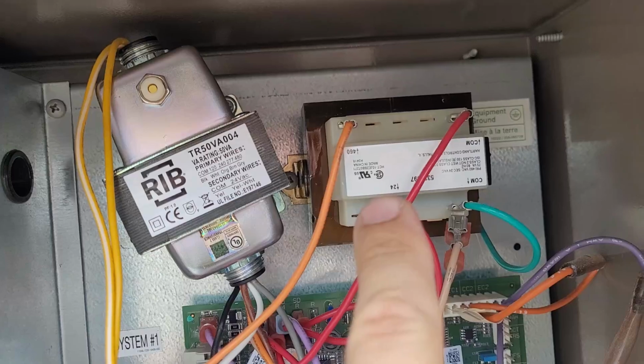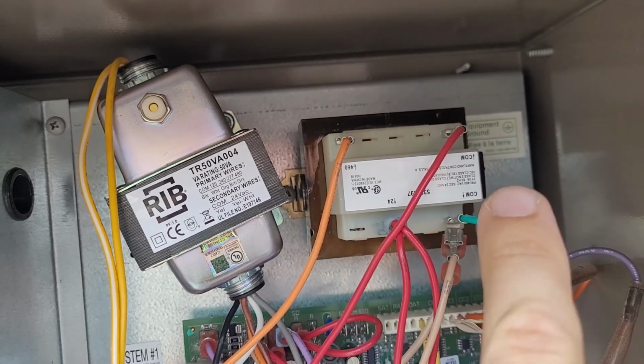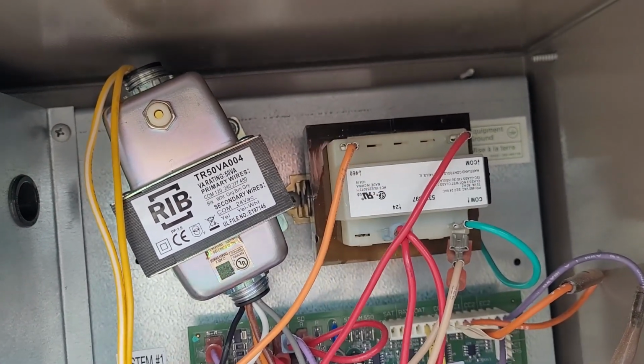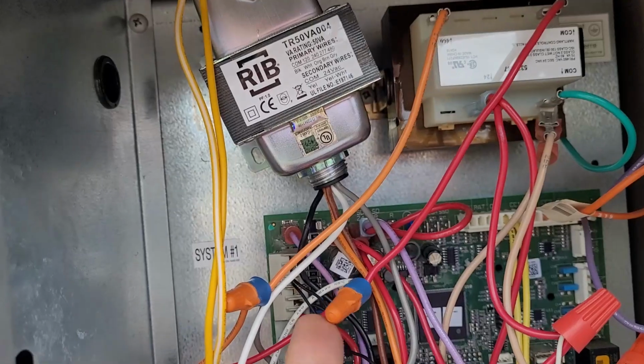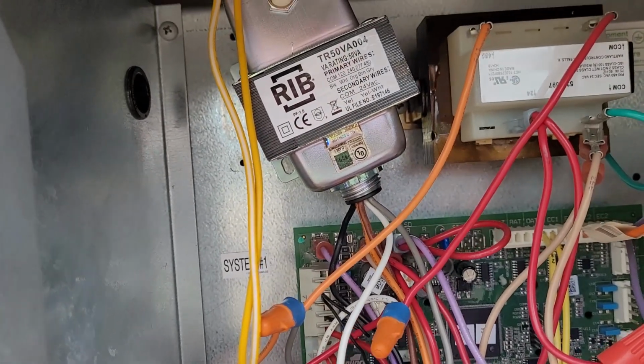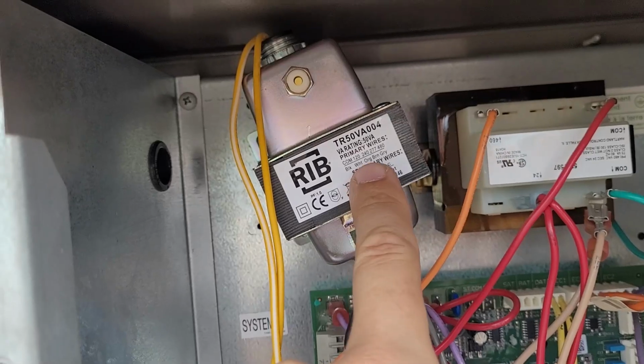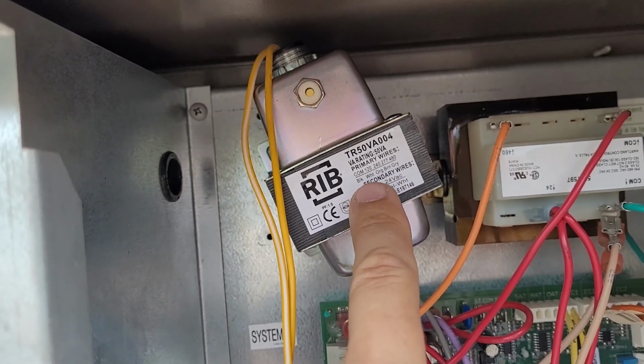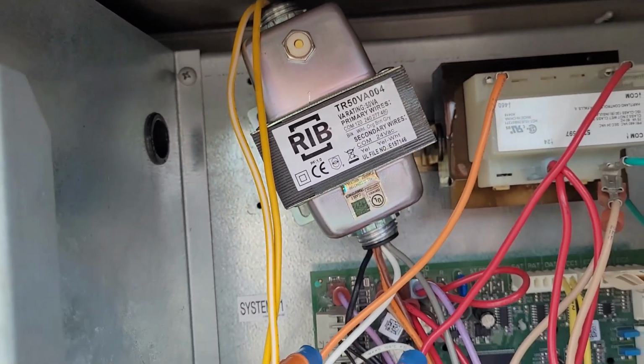So here's your power source, 460 volts between the red and the orange. So the red comes down and ties into white. White of our new transformer is actually the 120 tap. It should be using black for common, so there's your problem.